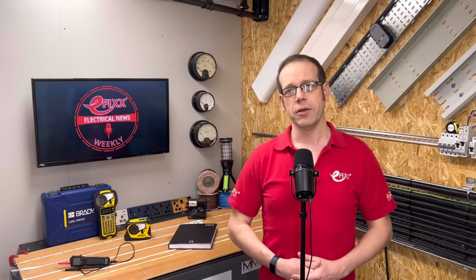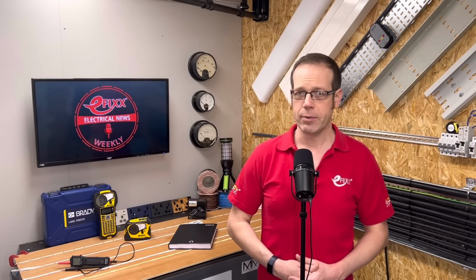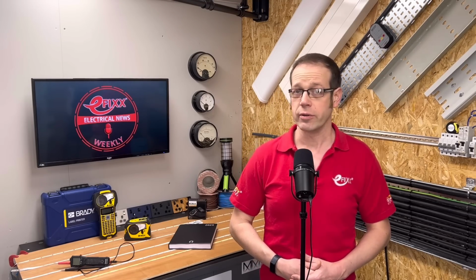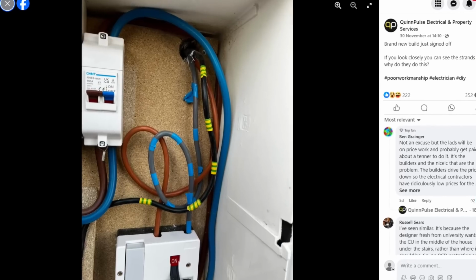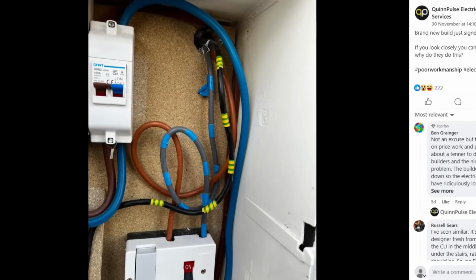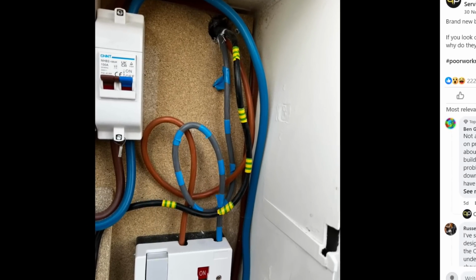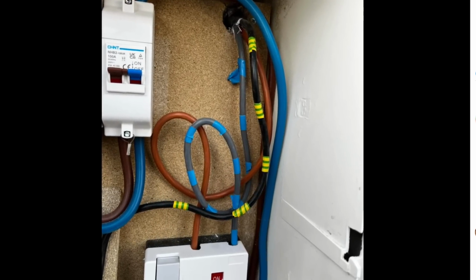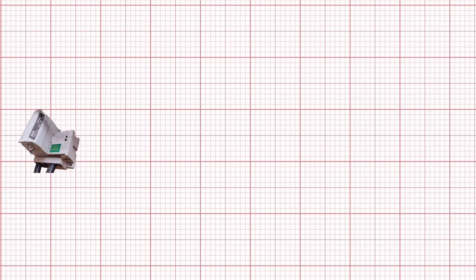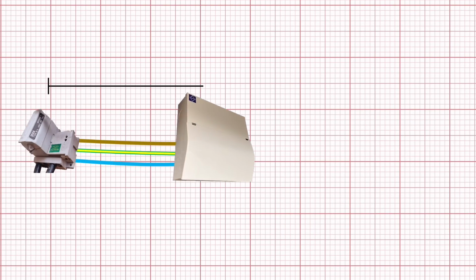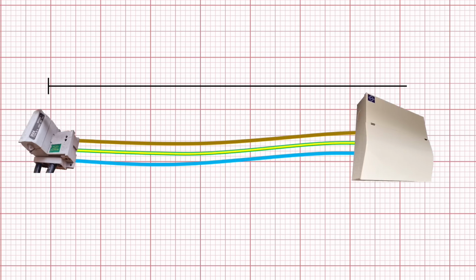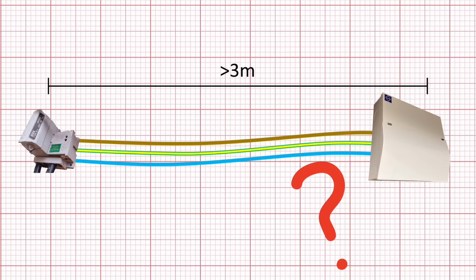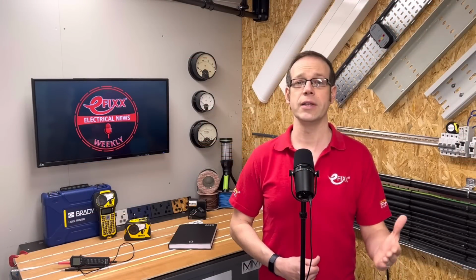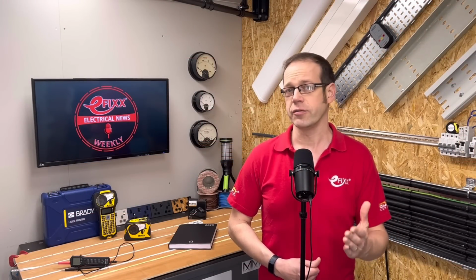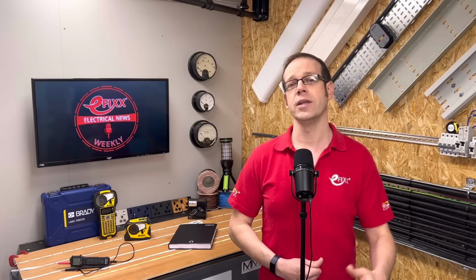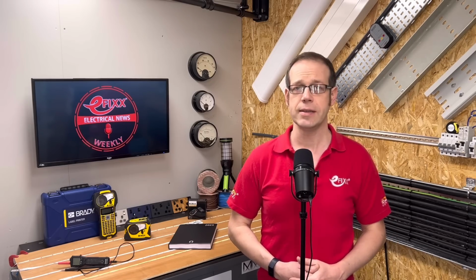Confusion reigns this week over the insulation of cables in meter cabinets. Reports indicate that new homes are increasingly featuring single insulated conductors within the external meter box. But opinion is sharply divided in the trade over whether this is acceptable practice. The problem arises if the consumer unit is more than 3 metres from the meter box. This requires installers to use some form of mechanical protection. The most common solution is to use steel wire armoured cable, but the cable is often stripped back and connected directly to an isolator or switch fuse inside the meter box.